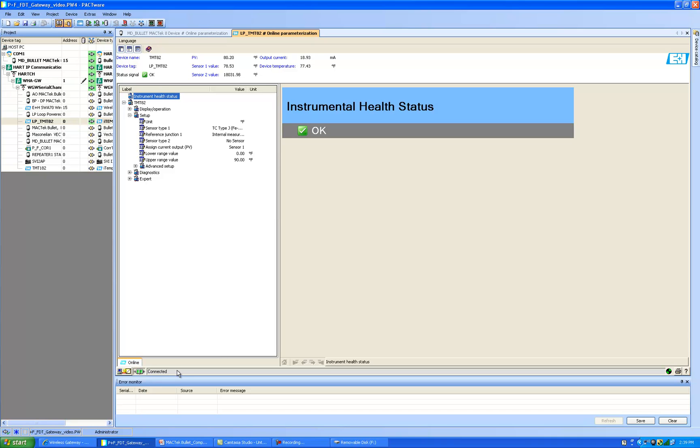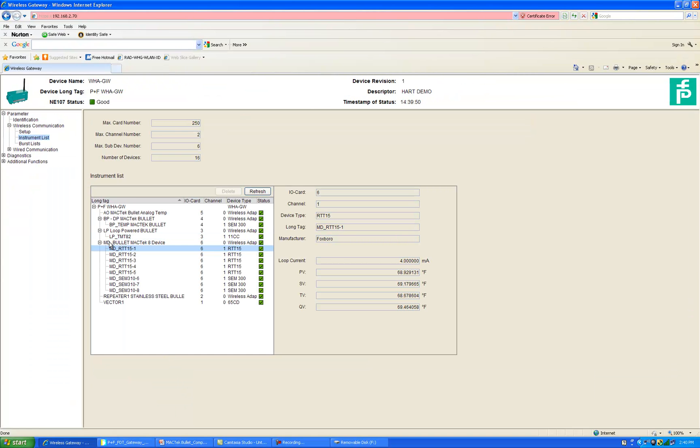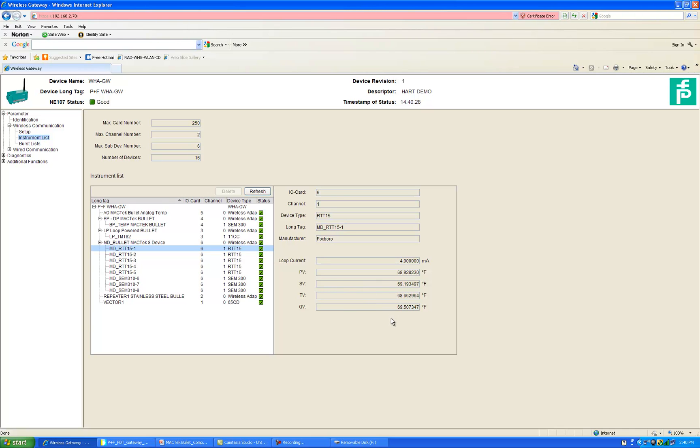So one last check before I leave you is I will check the gateway. So here we can see that the multi-drop bullet has joined and all eight devices are now attached and reporting values. The signals here are the PV for each of the devices is the average of my two thermocouples and thermocouple one is the SV, thermocouple two is the TV and QV is the electronics temperature. So I think you agree that we very quickly accomplished the task of adding a wireless HART adapter, the MacTech bullet to the gateway.